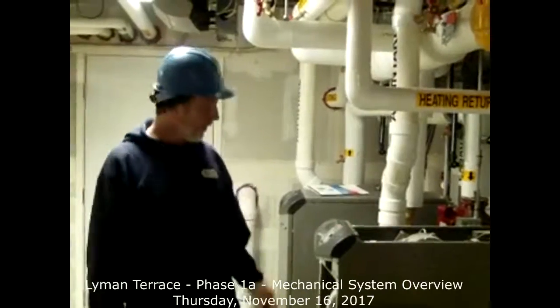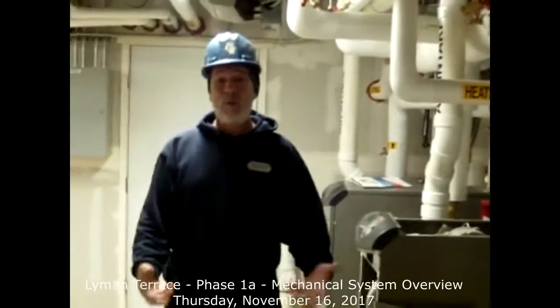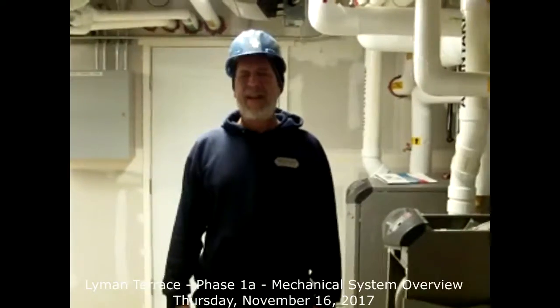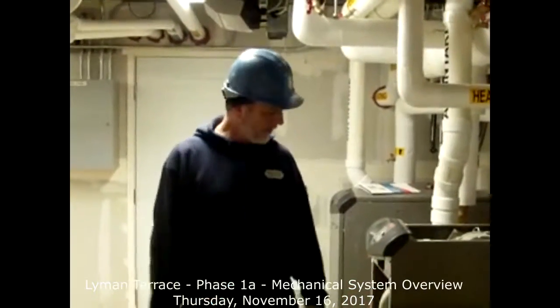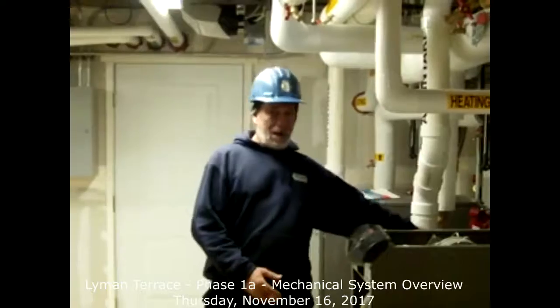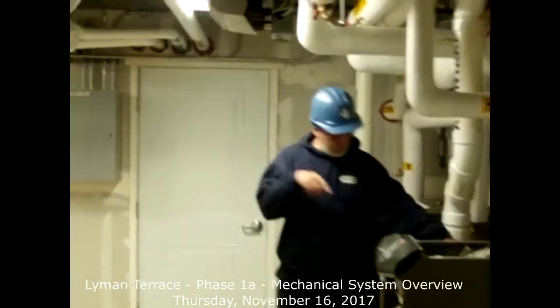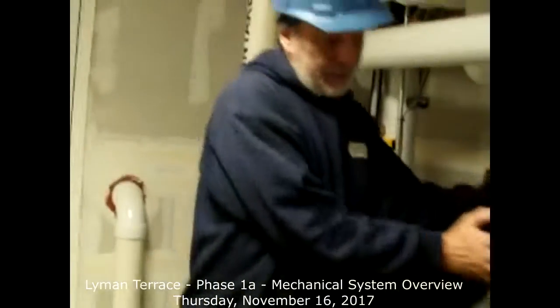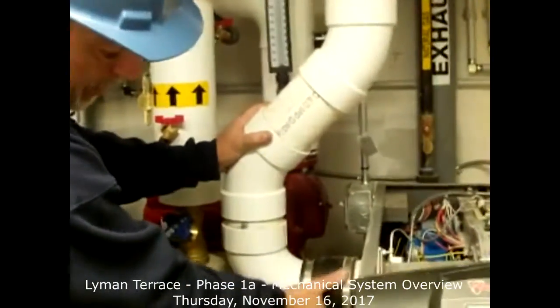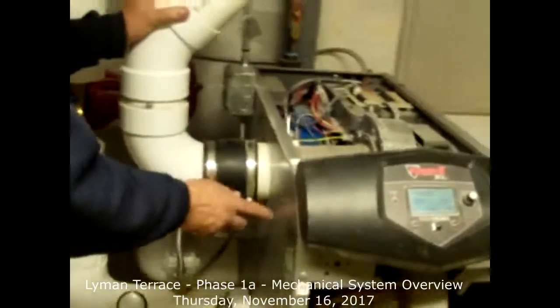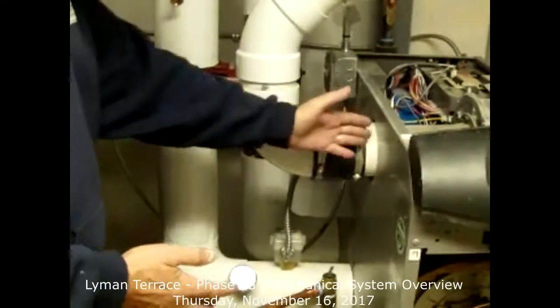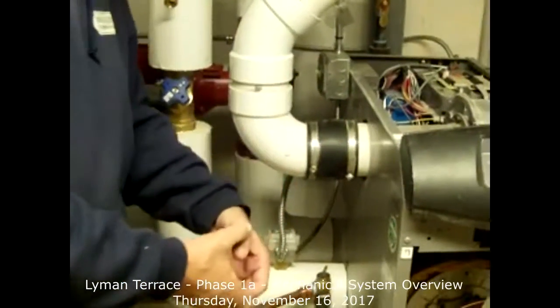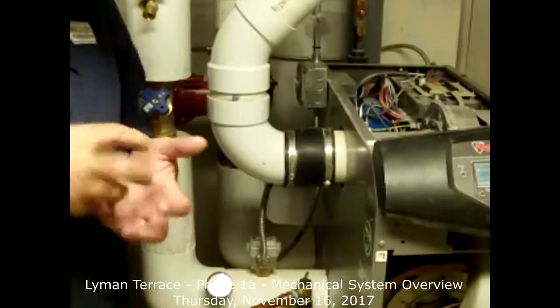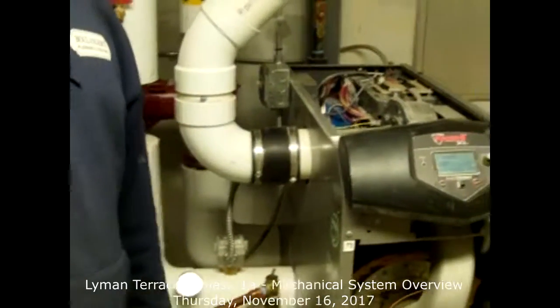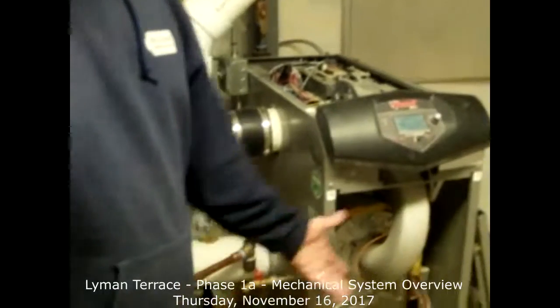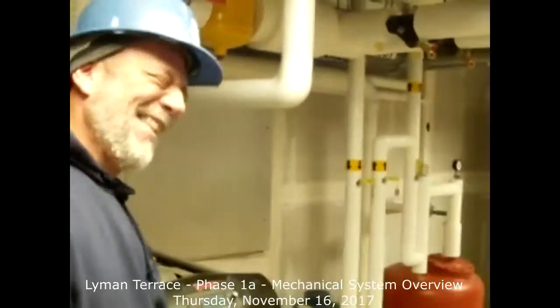The maintenance guy called me, he says, I've reset the boiler 3 times and it won't come on. And I said, okay, he says it's getting an air proving problem. I said, fine. I went out and I went, yeah, sure is. I took the coupler off here because it's very easy, if you wanted to film this, to check if anything's getting into there. This is a rubber coupler, okay? Little Fernco adapter, it looks like. Correct. This will come off, you can slide it, and you can visually look in, and stuck right inside of there was the container. I said, what is that? I took it out, I opened it, we had a good chuckle, but the maintenance guy made me give it to him. Yeah, great, thank you.